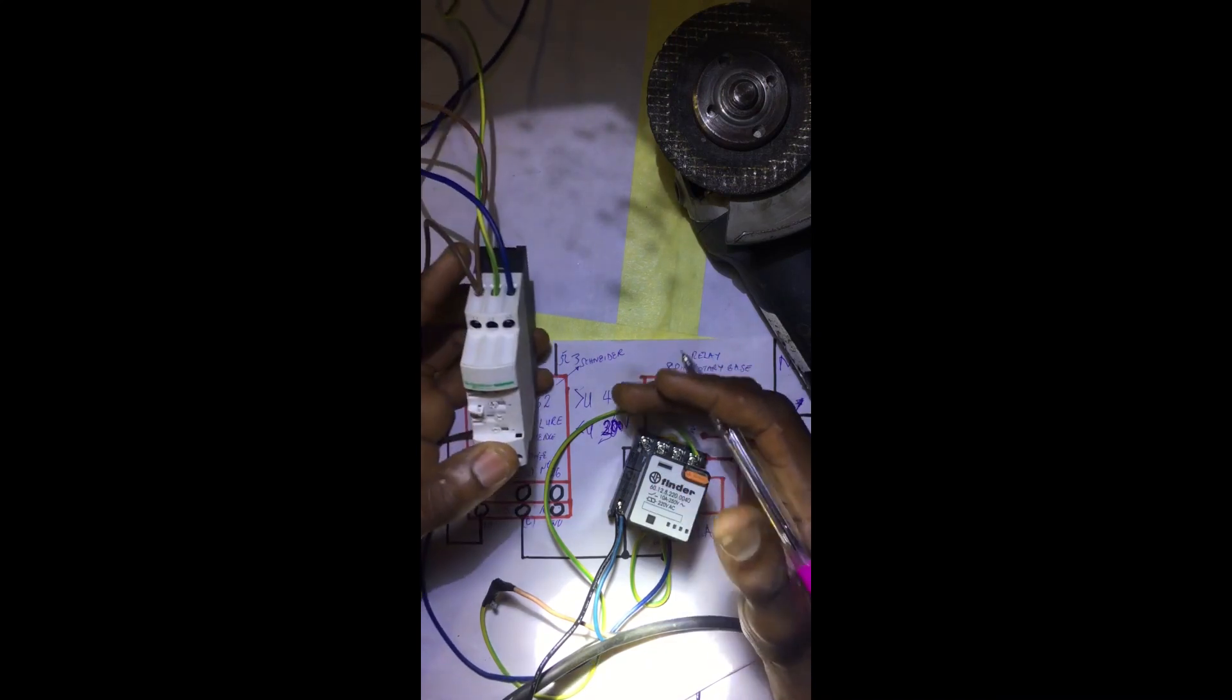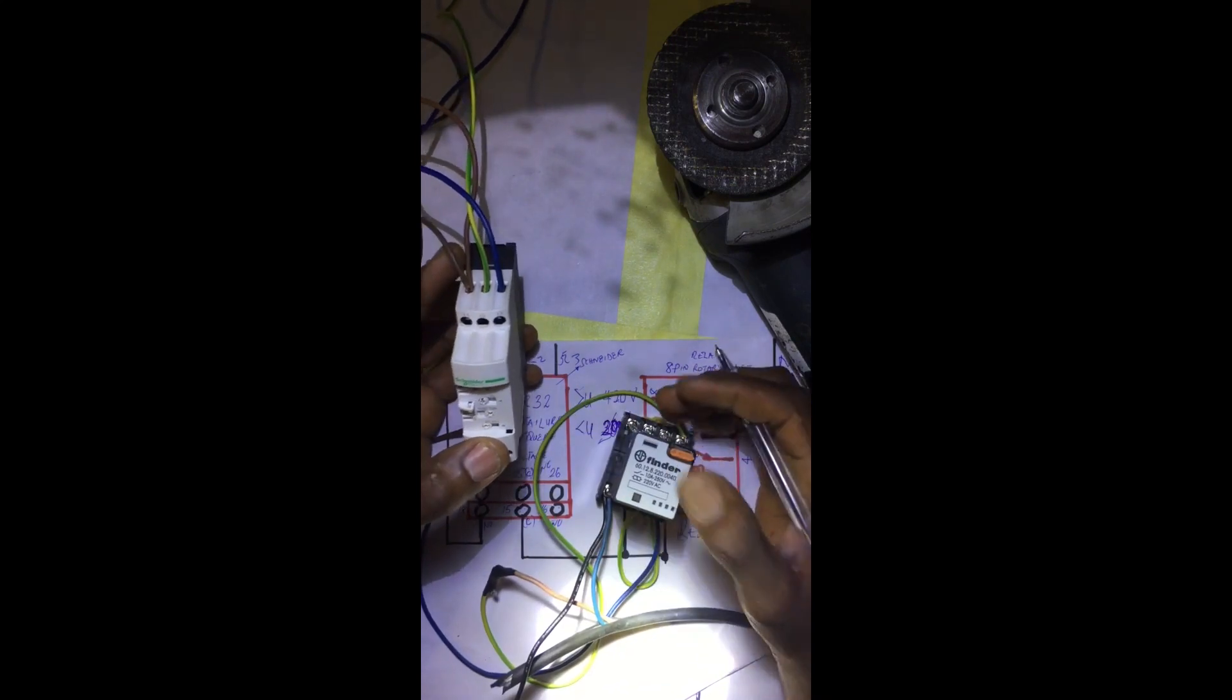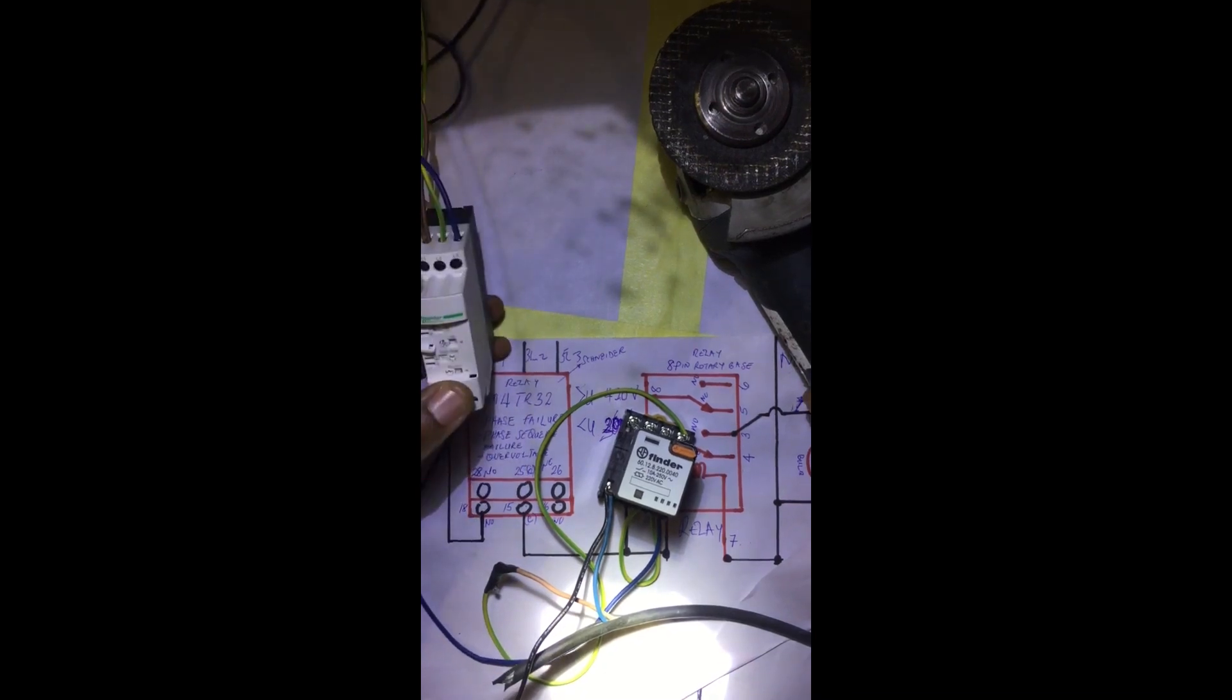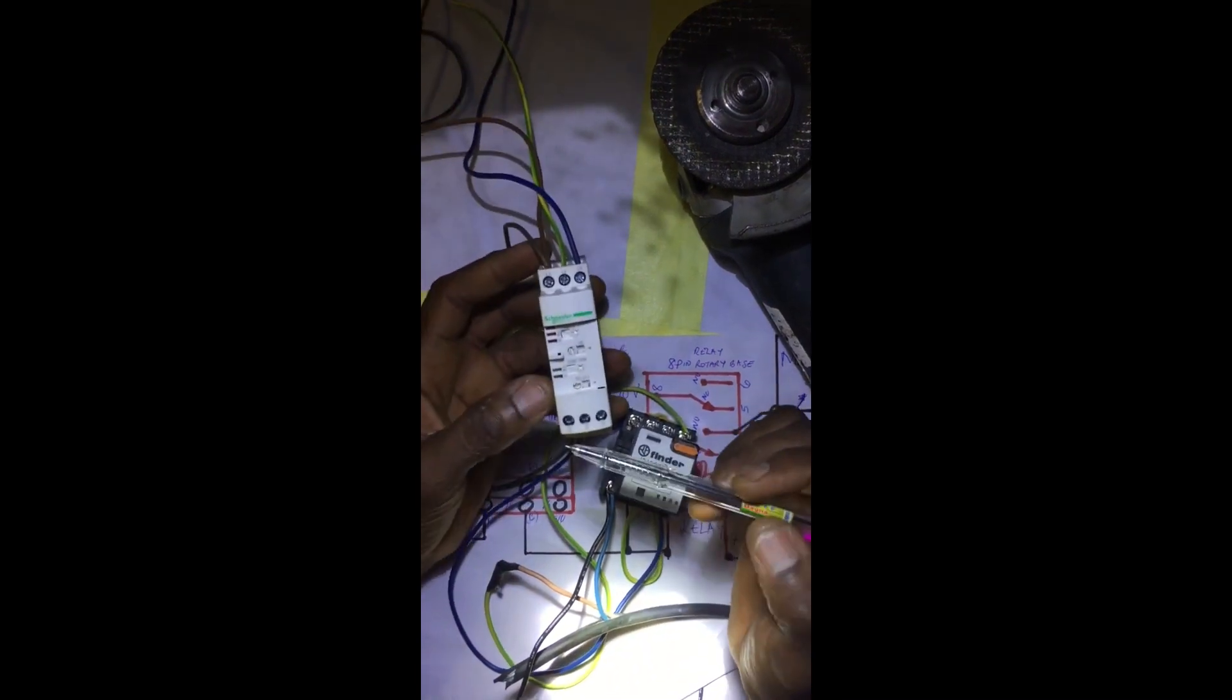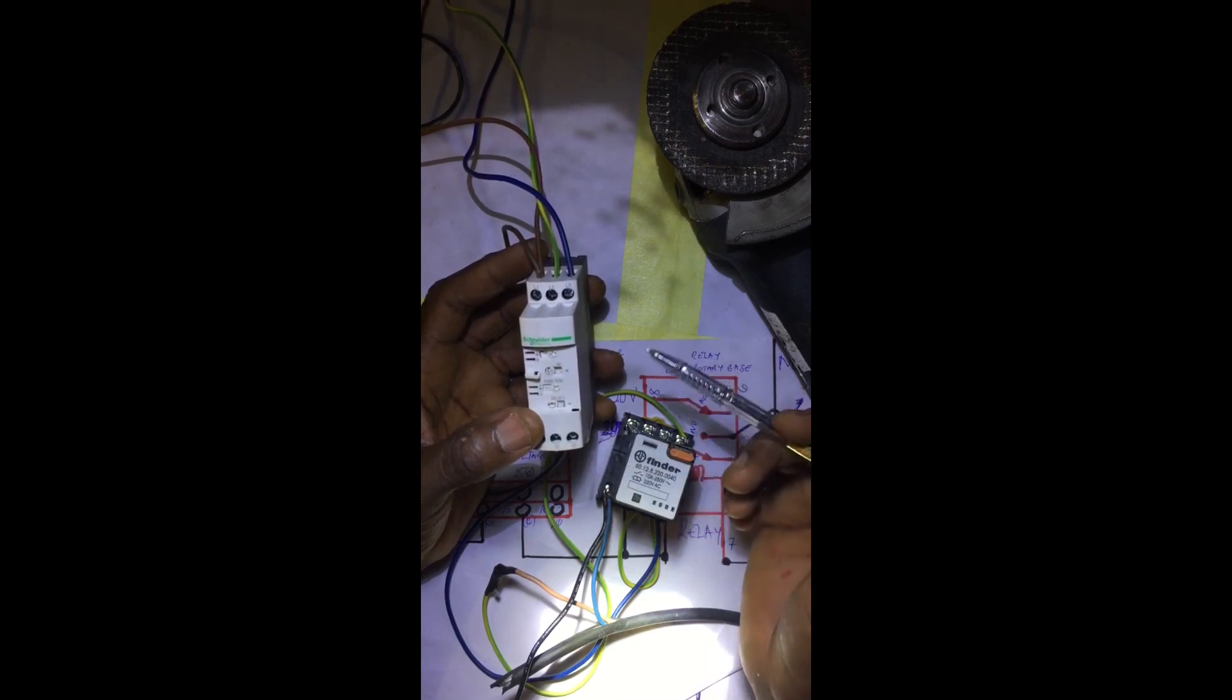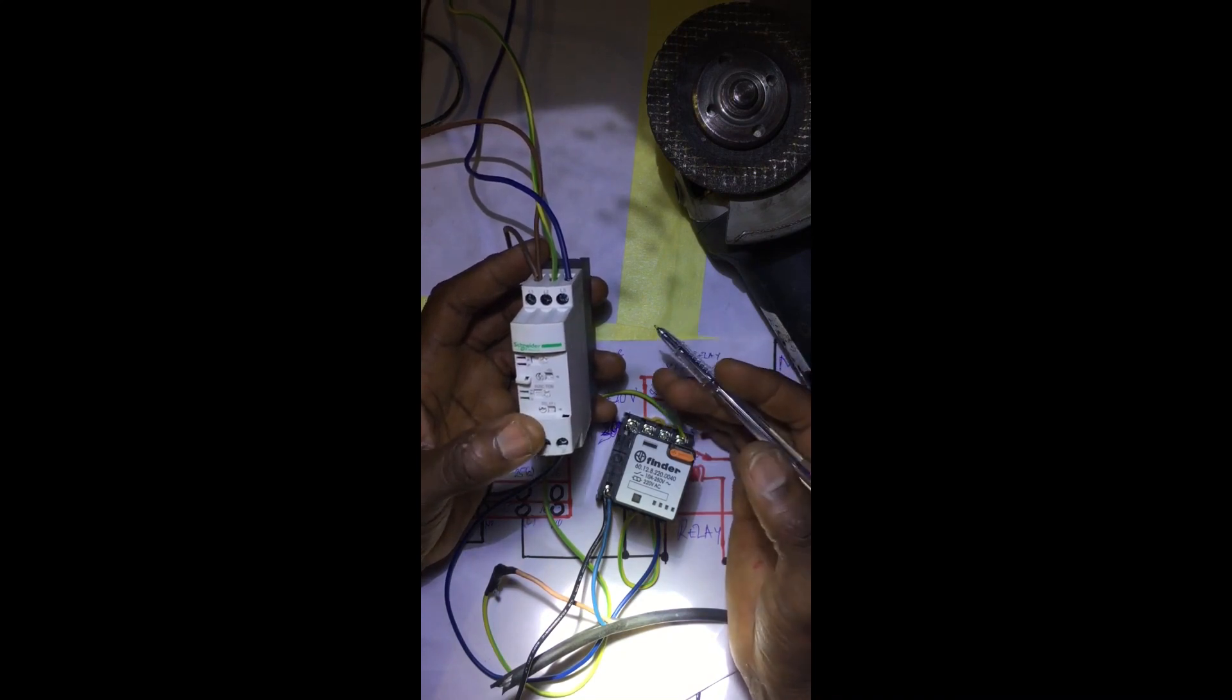For the purpose of this experiment or video, let's just consider it has been okay that we're using it for a single-phase load, which is a cutting machine. You can use this for three-phase load. The output of this conducting terminals 18 to 15 can be used to control a contactor which can release three-phase power supply to a motor of several thousand watts.